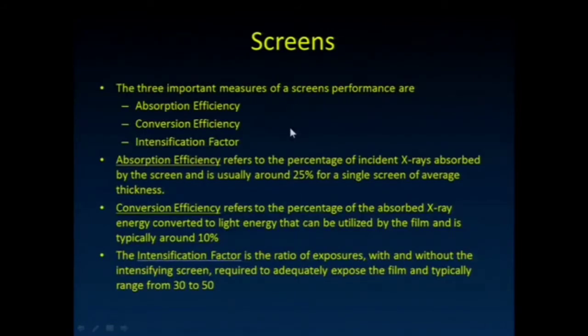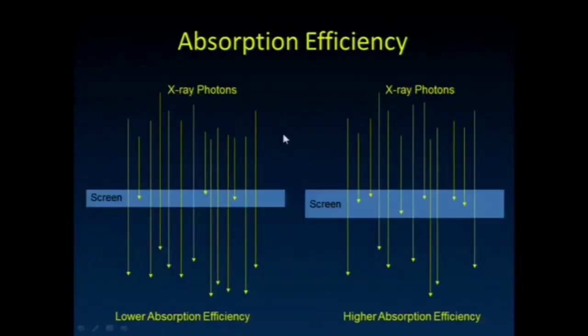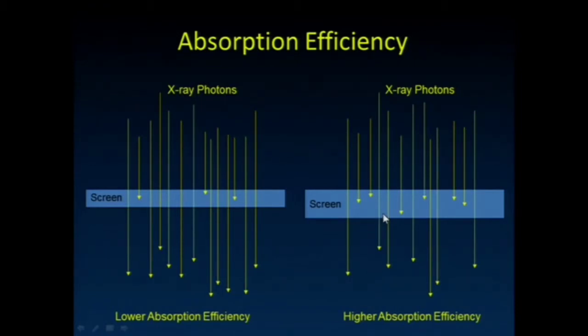When we talk about screens, we can talk about absorption and conversion efficiency — doing a better job converting some of that X-ray energy into lower energy photons that can be used to make the image. With absorption efficiency, if you just make the screen a little thicker, it'll now stop more of the X-ray photons and convert them to that lower energy light. The downside is there's now a thicker screen for that light to disperse in, so the light has more distance to spread out after it's generated, and your resolution properties go down a little bit with a thicker screen.